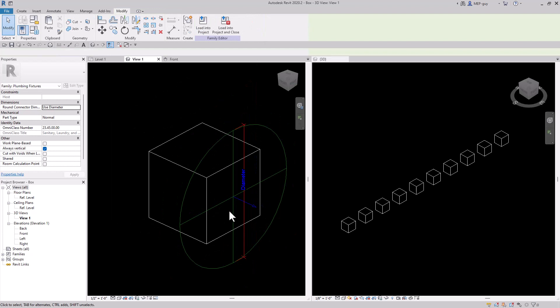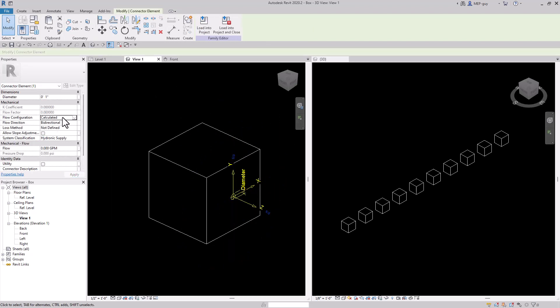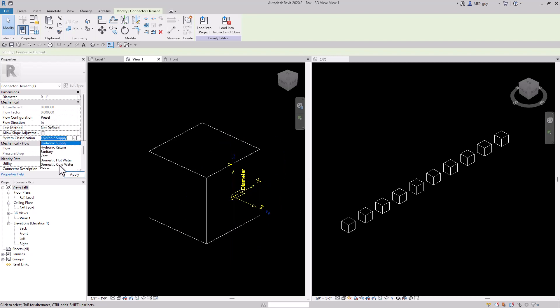We'll go to create pipe connector and we'll just click this face right here. We'll select our connector, change the diameter to one inch, and set the flow configuration to preset. Put the system on domestic cold water and for this example we'll just use one GPM.